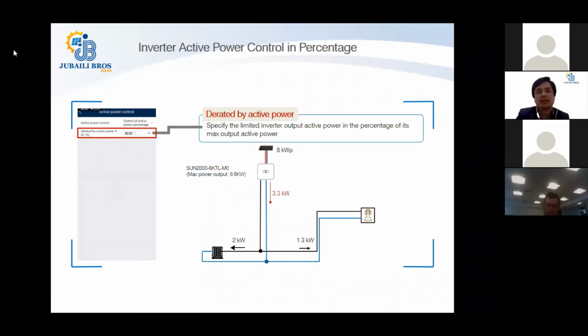So if you're limiting it to 50%, 50% of 6.6 is 3.3 kilowatt. So whatever the generation is, if it is more than 3.3, it will be limited to 3.3. If it is below 3.3, then the power will not be cut. So you can have an option of curtailing the output power of your inverter with the percentage. Such an option is available under the active power control option.